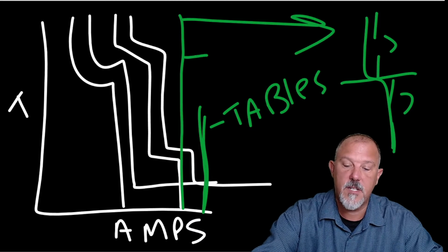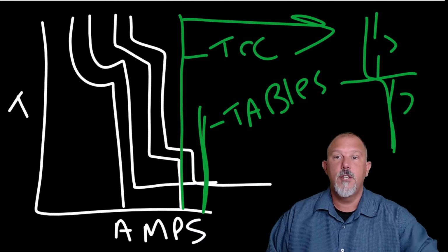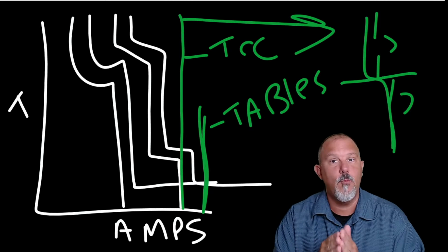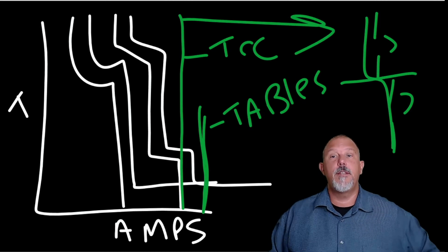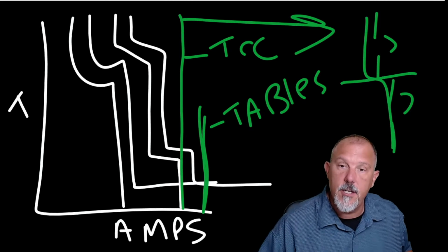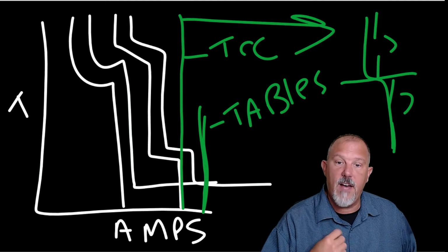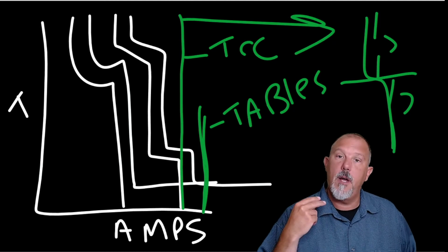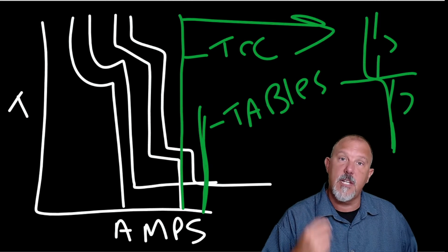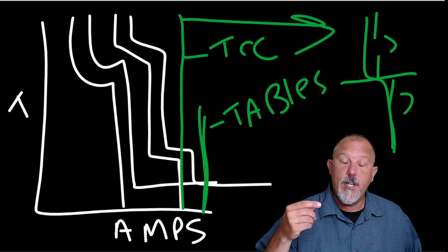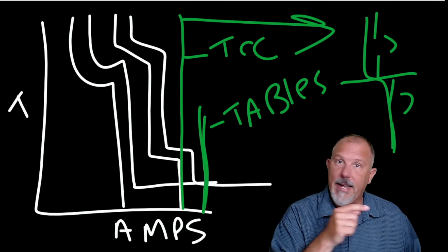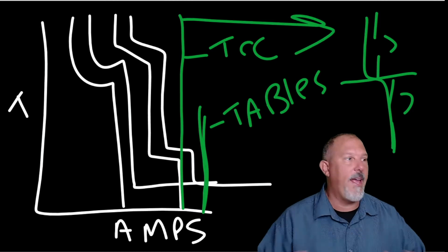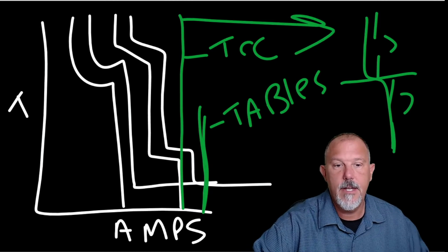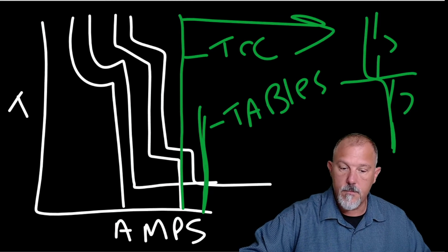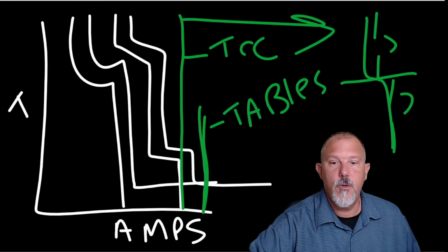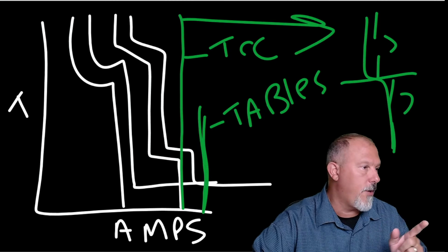And this is based upon the TCC. So one number, which will be higher than what you see on the curves, is going to help you understand when you will have enough fault current that will open both circuit breakers, and that's called a selective coordination study. And we do that in SKM, EDSA, EasyPower, whatever application you're in, and that's how we roll. So that's what his question was.